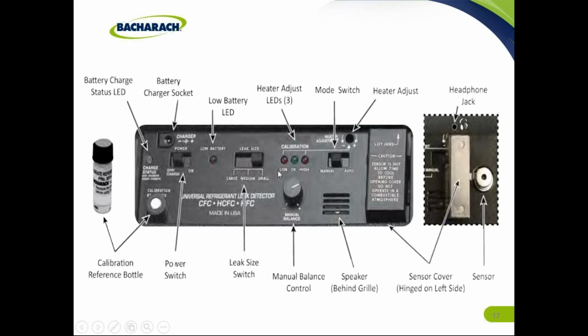If you swish it across there and it goes from low up to high LED and stays on high, that sensor is too hot, and you have to get a screwdriver, put it into this heater adjustment, and turn it counterclockwise to lower the heat going to that sensor. If you swish it across there and it just stays on low, that red LED, you don't have enough heat. So you have to go in here and crank it clockwise to put a little more heat on that sensor. Because ultimately you want to be able to swish this across this calibration gas, and it'll go from low to okay, back to low. Your adjustment's good.